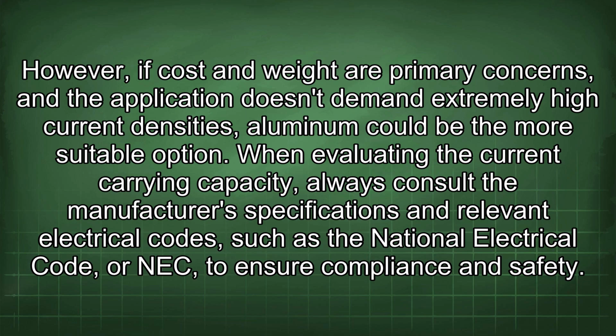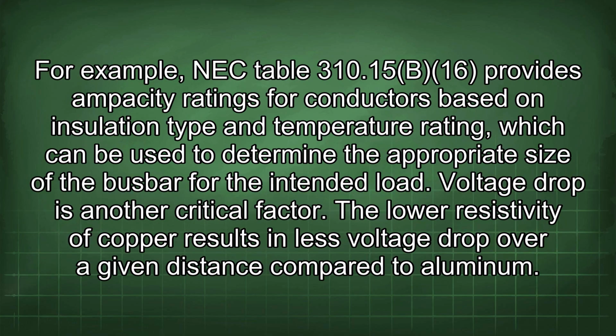the more suitable option. When evaluating the current carrying capacity, always consult the manufacturer's specifications and relevant electrical codes, such as the National Electrical Code, or NEC, to ensure compliance and safety. For example, NEC Table 310.15(B)(16) provides ampacity ratings for conductors based on insulation type and temperature rating, which can be used to determine the appropriate size of the busbar for the intended load.